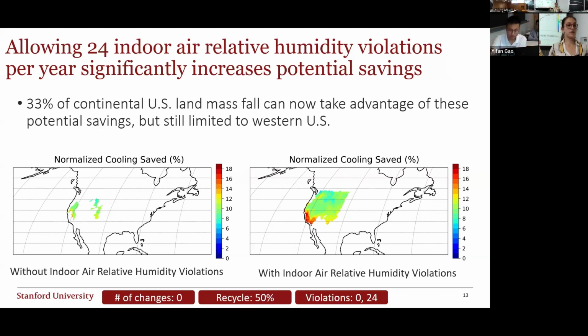This would mean changing the supply air temperature of the air handling unit up to 59 degrees instead of 55. This is exciting because this set point change doesn't cost any money - you're already paying somebody to run your HVAC system, you're just telling them to prioritize this, once forever, and you can find these savings.